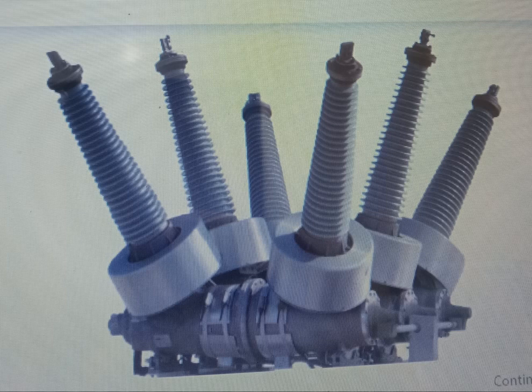Another thing is that we have to de-ionize the medium as early as possible. If the medium between the contacts is de-ionized quickly, the possibility of restriking can be reduced significantly. For de-ionization, we can follow different methods: increasing the gap between the contacts, increasing the pressure, cooling the arc, and gas blast effect.